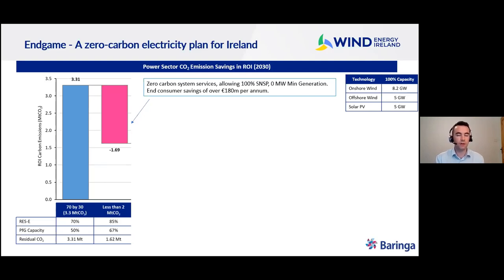That's effectively where we're able to remove the need for fossil fuel generation being turned on at all times to provide services to the grid, like voltage support, inertia, and reserves. If you can do that, you can operate your power system at 100% SNSP and what's called zero megawatts minimum generation — basically meaning you don't need a thermal or fossil fuel plant on the system to provide these services.